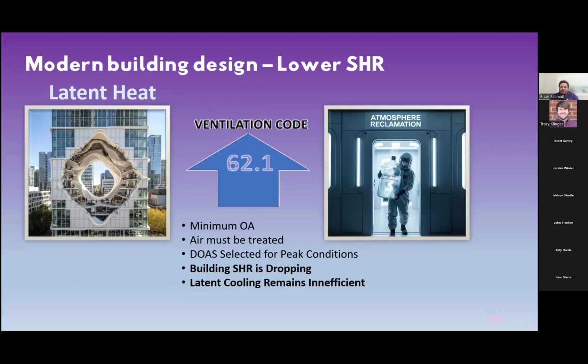So we have minimum outside air requirements, as everyone on this call is aware of. Air must be treated. You're going to select your DOAS for your peak condition. But again, overall, the building sensible ratio is dropping. And so latent cooling remains inefficient. Again, allowing very efficient sensible systems to become even more efficient. The way to do that is to allow a system that is very efficient to take care of the latent load in the building.